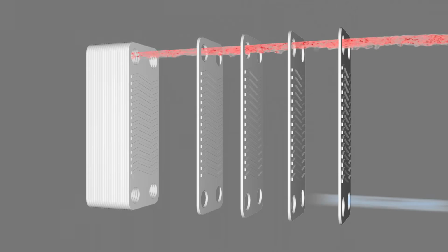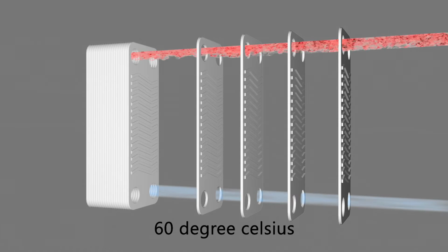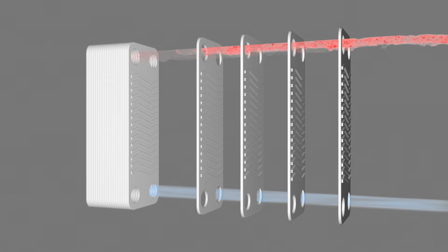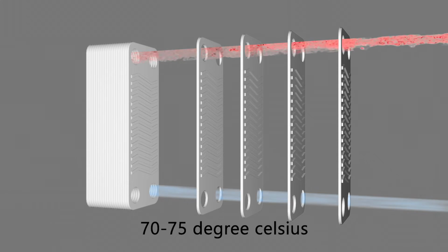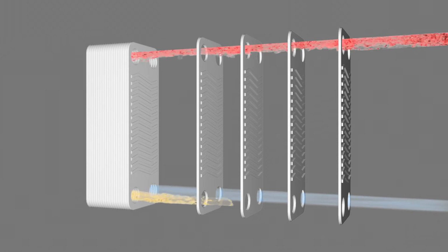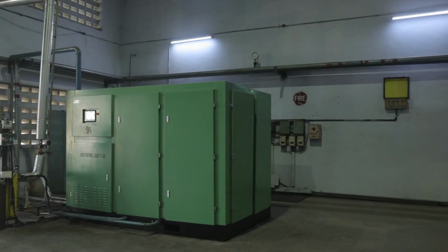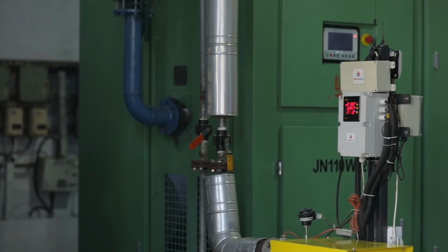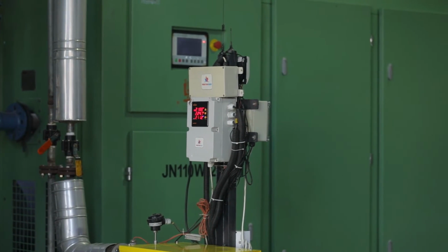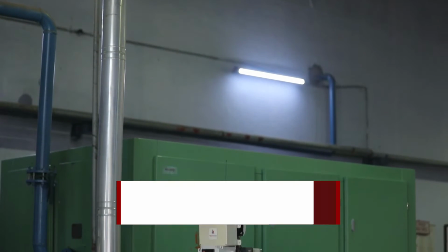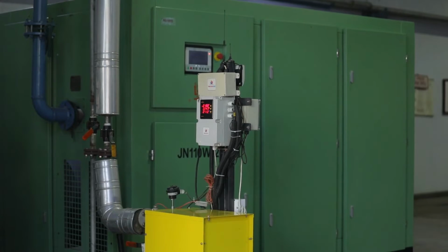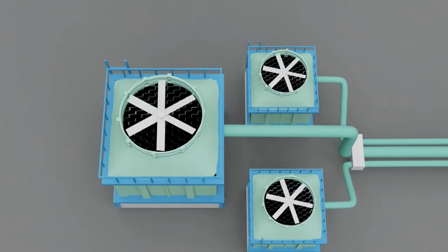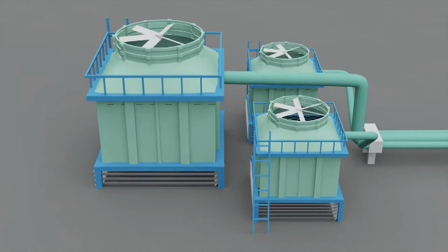It flows counter to the water at 60 degrees Celsius, flowing in the right pipe in the unit. The heat energy from the oil gets absorbed by the flowing water and gets heated to 70 to 75 degrees Celsius. The oil returns to the oil cooler at the screw element. The double walls of the heat exchanger ensures that there is never any intermixing of oil and water. This unique and innovative system has led to three main benefits over the conventional system used for air compression. By using the screw compressor for waste heat recovery, hot water generation at 70 degrees centigrade has been achieved. Energy saving on account of cooling tower has been achieved as the extra heat is now utilized.